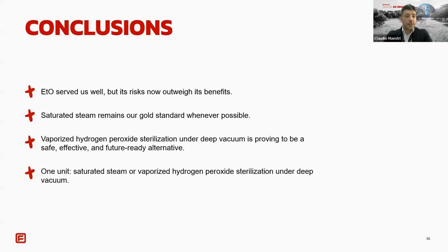Vaporized hydrogen peroxide under deep vacuum is a reliable solution for complex and sensitive types of items, ensuring both microbiological effectiveness and material compatibility, offering an effective alternative to ethylene oxide sterilization. With its flexible process parameters, like we have seen, number of pulses, H2O2 amount, deep vacuum target, holding time, the deep vacuum H2O2 autoclave allows adaptation to ensure process effectiveness and optimization of the H2O2 sterilization cycle.